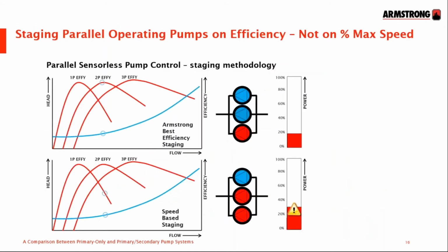If we take it a step further and go to the 25%, we'll do that after we have a little look at the staging of the parallel pumps. We've taken for granted that we've got parallel pumps in operation here using headered pumps. What we want to talk about now is how we control them. The traditional way of controlling pumps is by staging in extra pumps on demand when they approach maximum speed, and staging them out when demand is dropping at minimum speed.